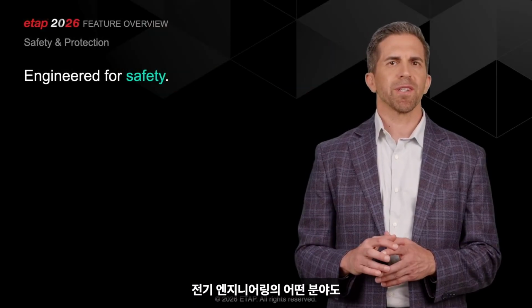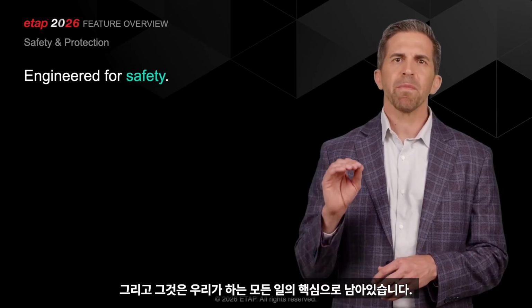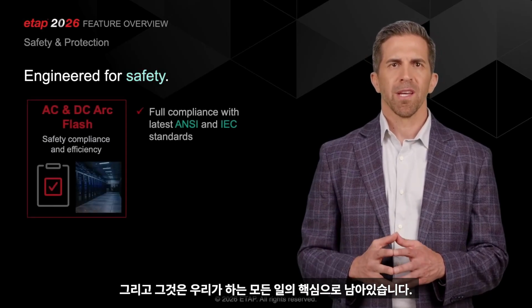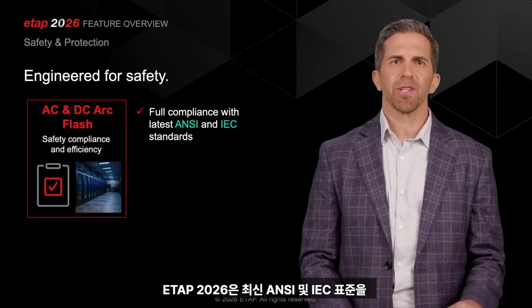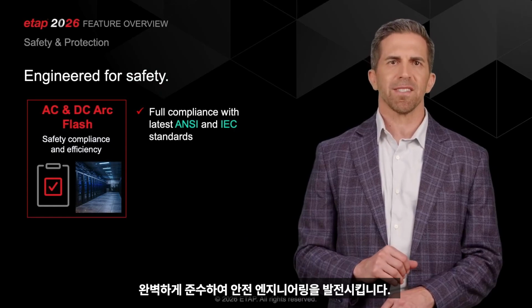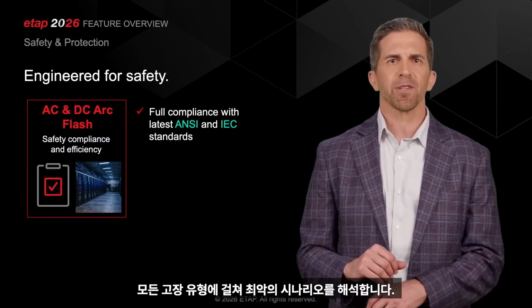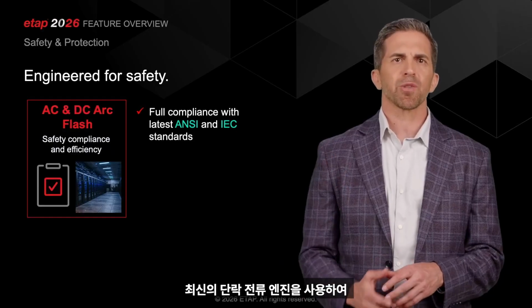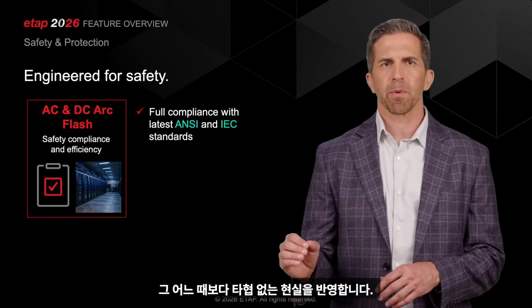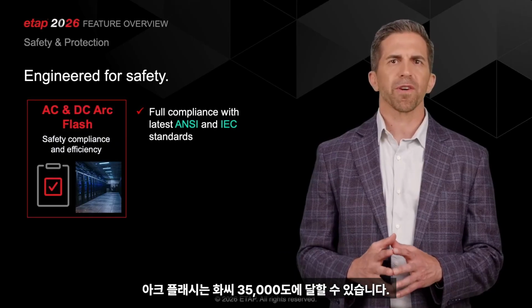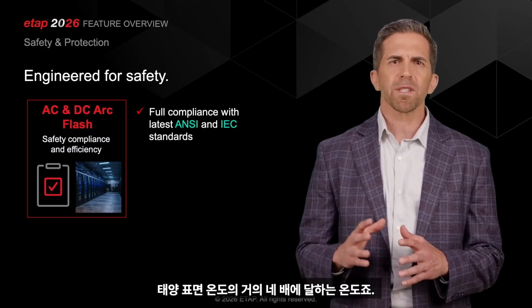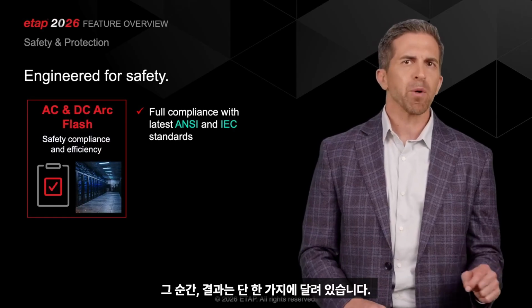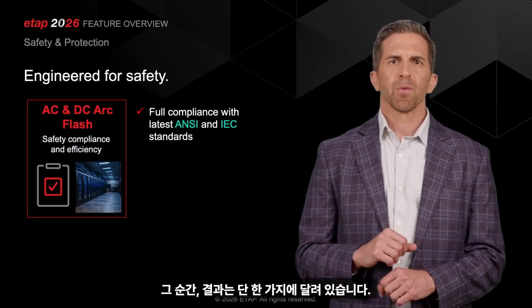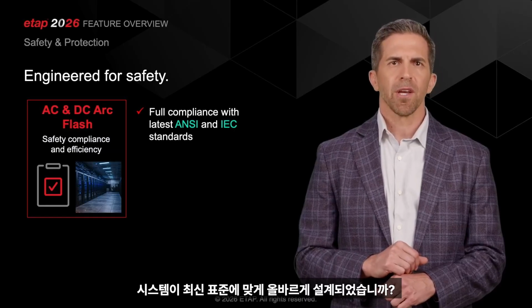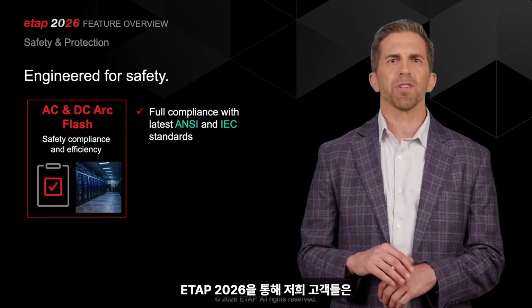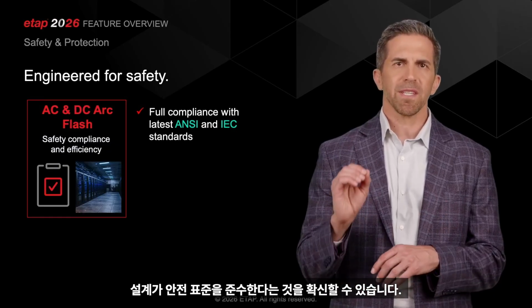No discipline in electrical engineering carries higher stakes than safety, and it remains at the core of everything we do. ETAP 2026 advances safety engineering with full compliance with the latest ANSI and IEC standards, analyzing worst-case scenarios across all fault types, using the latest short-circuit engine, because the reality is uncompromising. An arc flash can reach 35,000 degrees Fahrenheit, nearly 4 times the surface temperature of the sun. In that moment, outcomes depend on one thing. Was the system designed correctly to the latest standard? With ETAP 2026, our customers can be assured that their designs comply with safety standards.